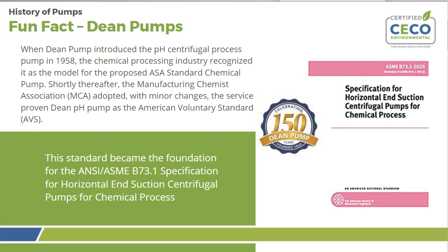The ANSI spec is a design and specification standard for horizontal end suction centrifugal pumps. ANSI pumps manufactured by different companies are dimensionally interchangeable. What it ultimately means for the end user is that it allows the end user to switch brands without affecting piping location, the motor attachment, coupling, and/or base plate dimensions.